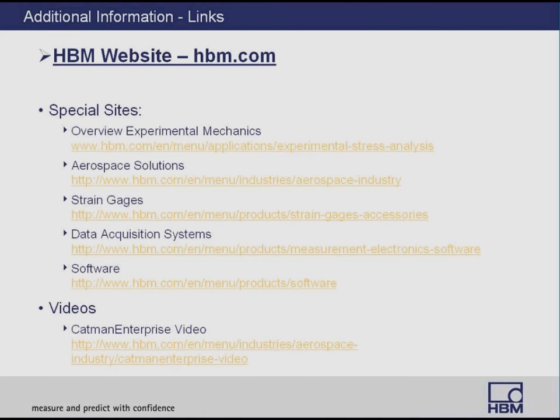All right, we've got a few follow-up questions here on that topic. Can the TID or TEDS be used on older sensors like load cells? Yes. I mean, TID can be used for any sensor, and of course it must be supported by the digital amplifier system to be read out.